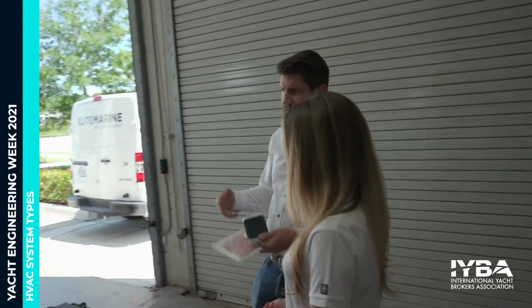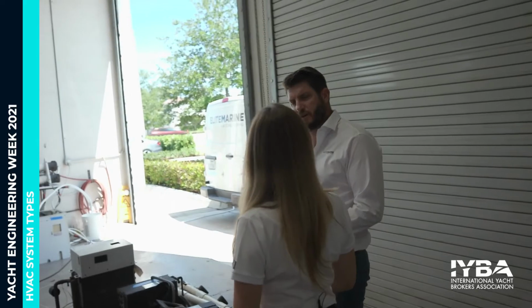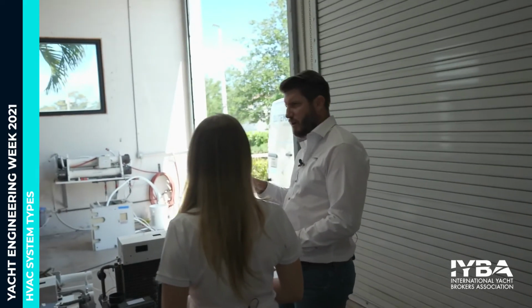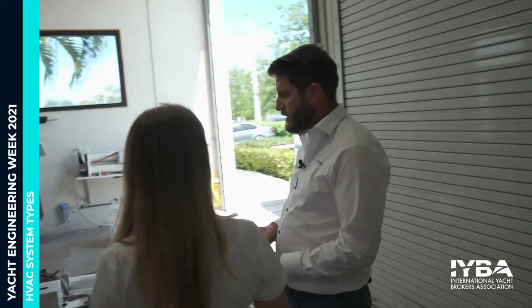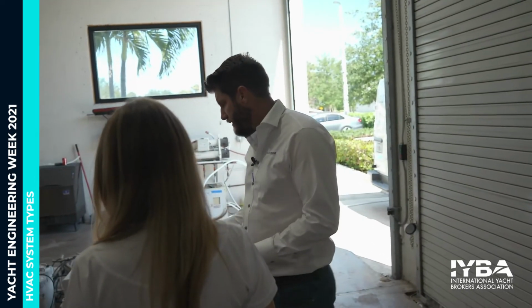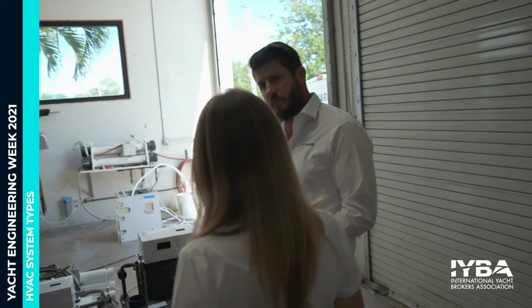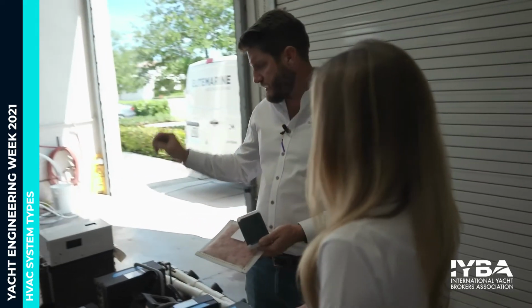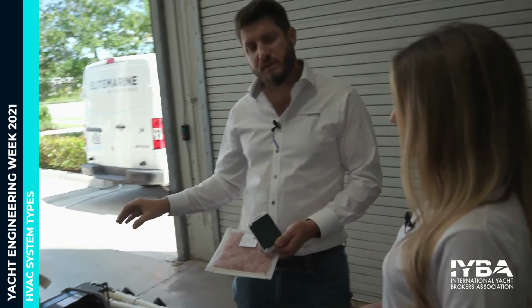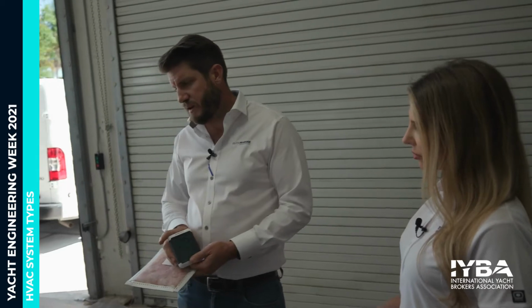The customer could go buy standard dehumidifiers, but they're kind of bulky and ugly. The other way is we now have new controls that we can install in each cabin. What the controls do is, as they're cooling, they pulse the heat strip inside the air handlers. That keeps the cooling process lasting longer, which brings even more moisture out of the air, which in turn keeps that moisture level below 60%. So 60% is the sweet spot we want to stay below.